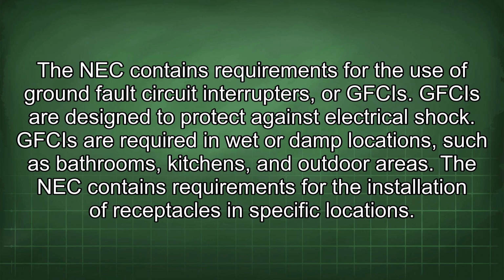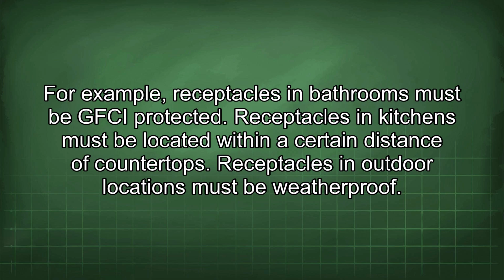The NEC contains requirements for the use of ground fault circuit interrupters, or GFCIs. GFCIs are designed to protect against electrical shock. GFCIs are required in wet or damp locations, such as bathrooms, kitchens, and outdoor areas. The NEC contains requirements for the installation of receptacles in specific locations. For example, receptacles in bathrooms must be GFCI protected. Receptacles in kitchens must be located within a certain distance of countertops. Receptacles in outdoor locations must be weatherproof.